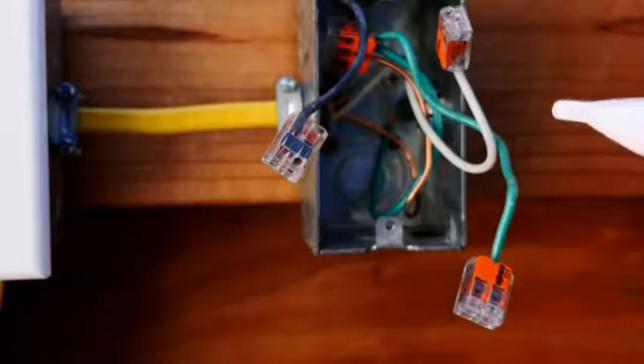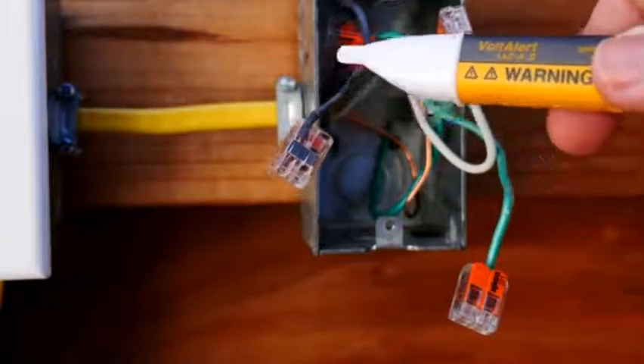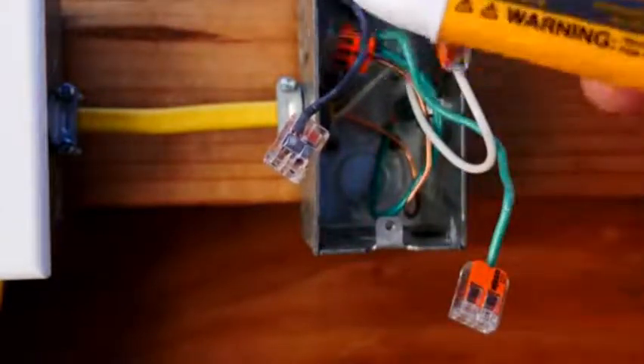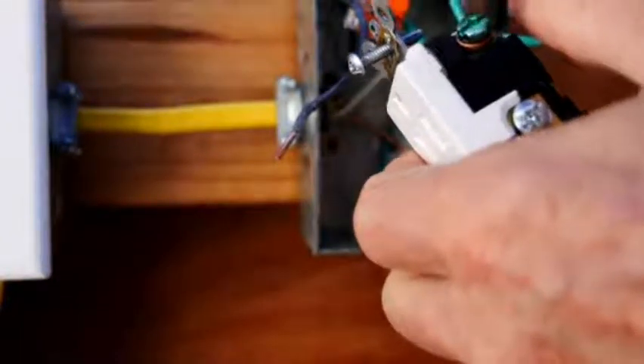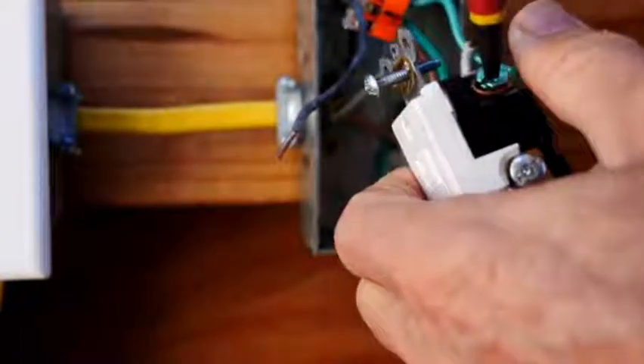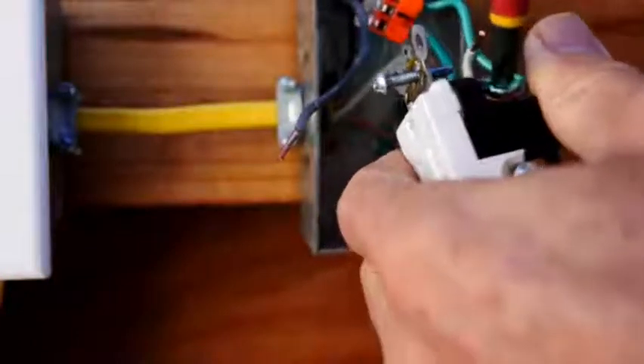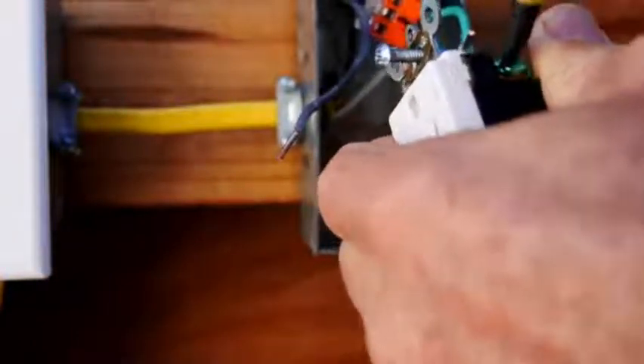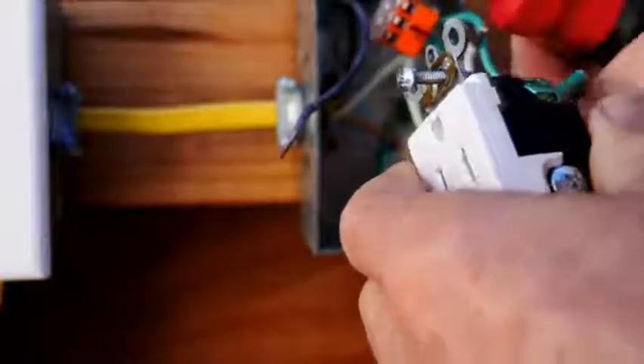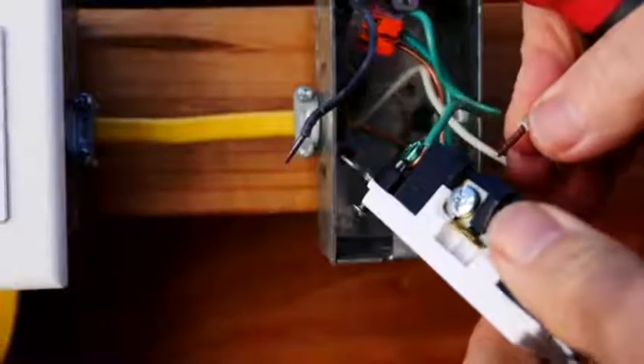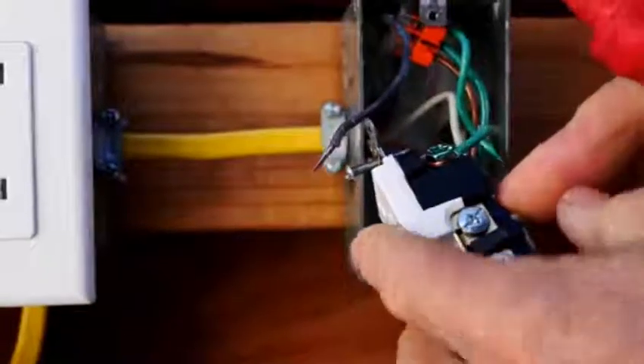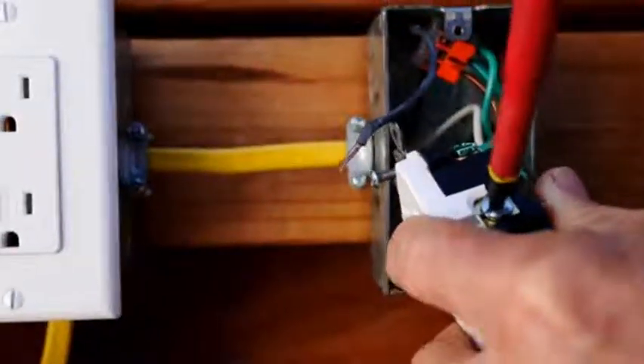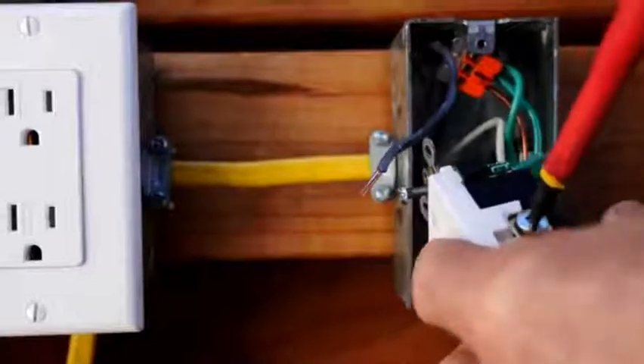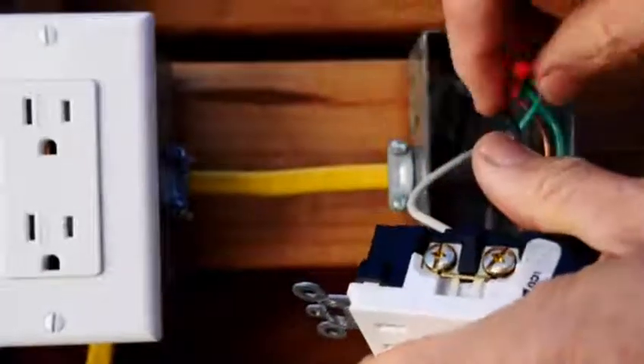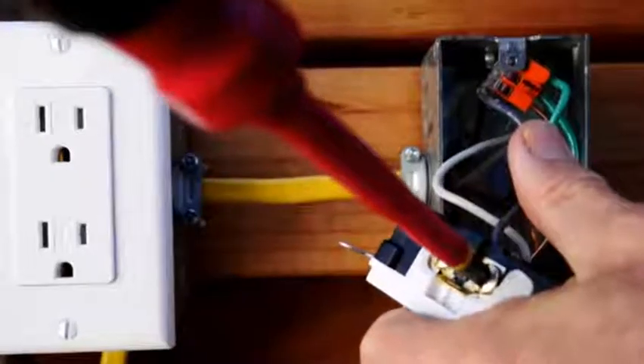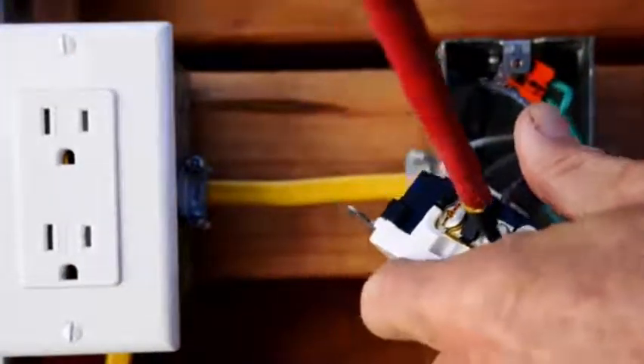I've turned off the circuit breaker, and I'm going to do a double check to make sure that everything is off. Now with the circuit breaker off, I am hooking the receptacle back up, and I put the green ground wire around the green terminal. I'll tighten it down securely. And this time I'm going to make sure that the white neutral wire goes to the silver terminal. And I'll tighten that down securely. And the black hot wire goes to the bronze terminal. And I'll tighten that one down securely.